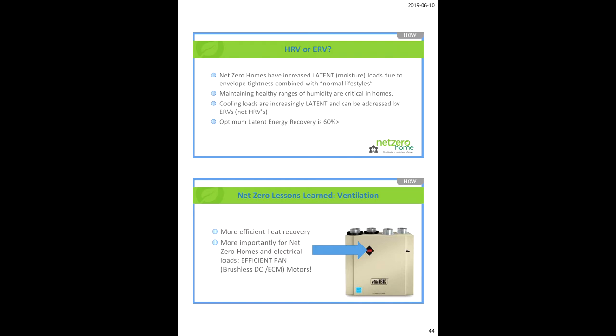Broan, Nutone, these manufacturers, without telling you, have started to put low-volt taps in the back of the range hoods, and what they're there for is to connect a low-volt wire down to the basement or utility room where they have a hole in the wall. It's a mechanically operated damper, it's really complicated. When the fan turns on, the hole opens up, and when it turns off, it closes.